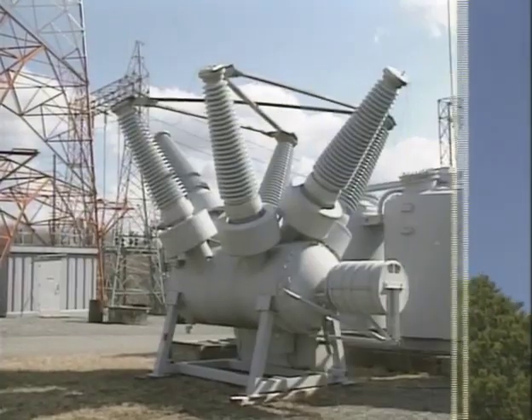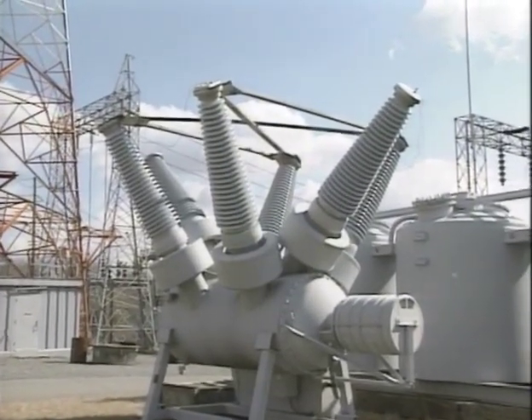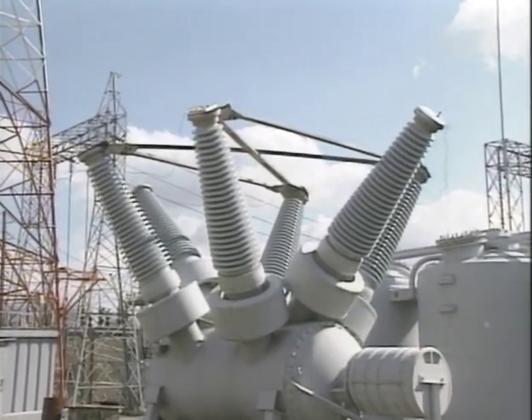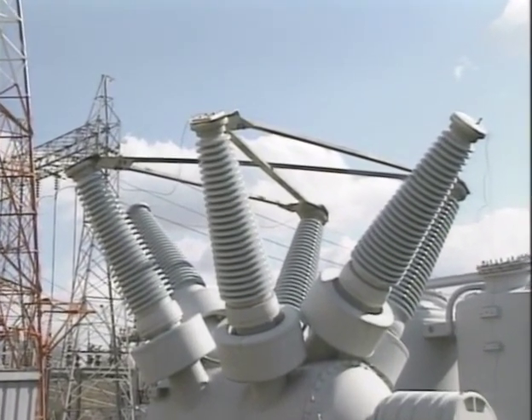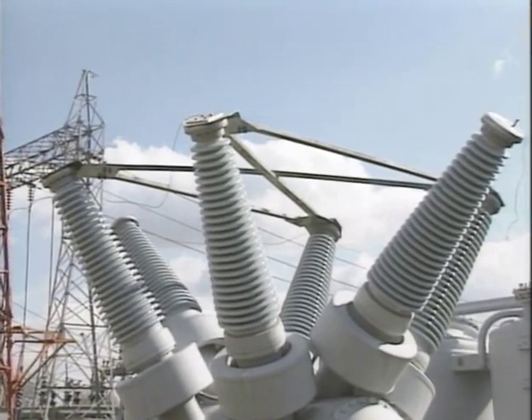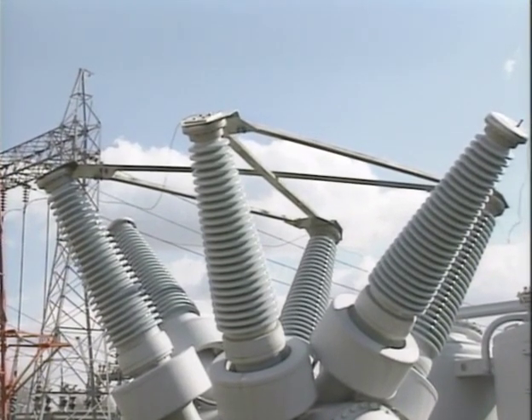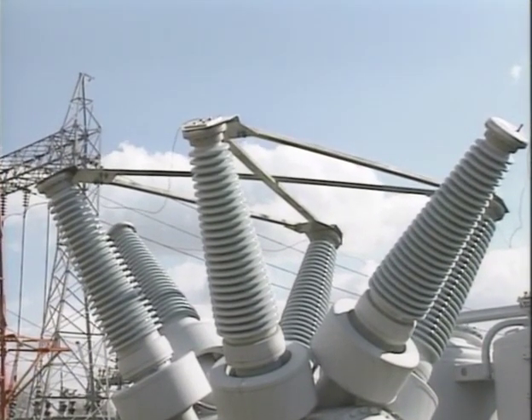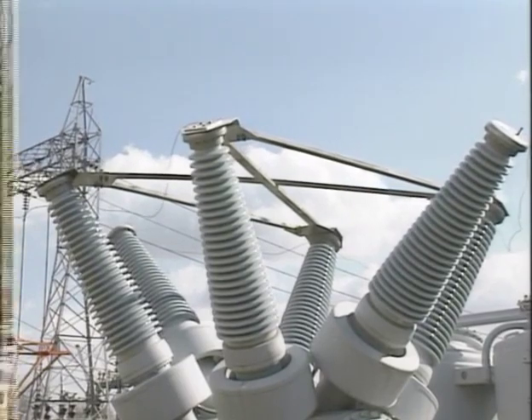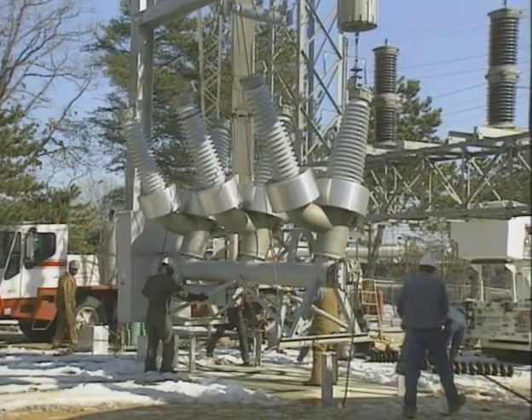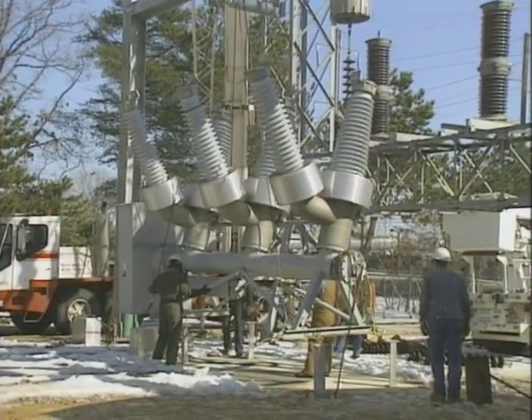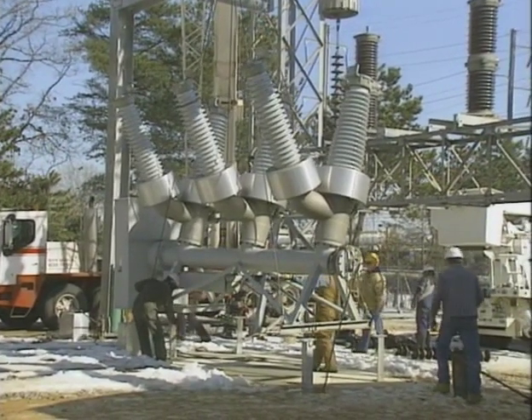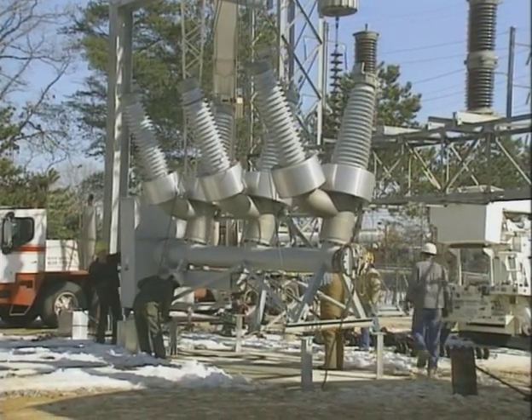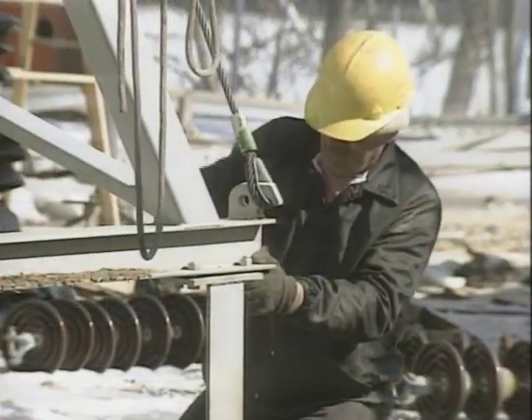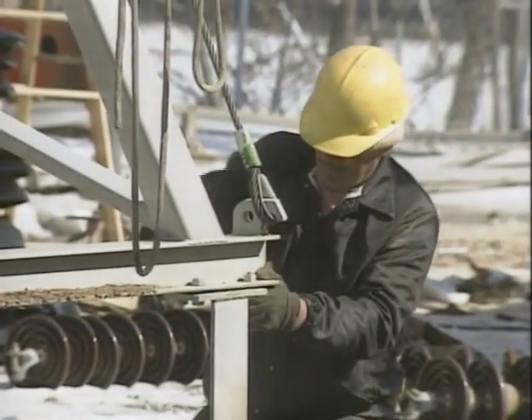structures. Some breakers may have additional braces or shipping framing that were installed to reinforce the breaker during shipping. The additional braces are typically left on until the breaker is set on its pad, positioned, and bolted down. When the breaker is placed on its pad, it's set down carefully to ensure that it doesn't tip over and that it lines up properly with its anchor bolts. Then the breaker is secured to its foundation.